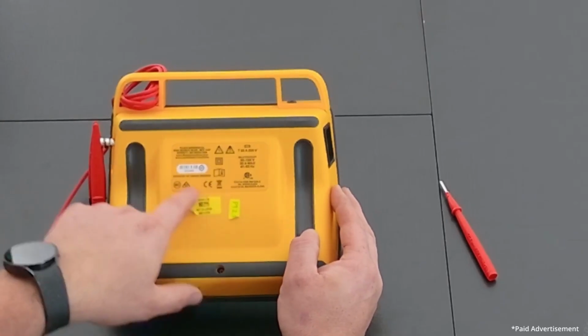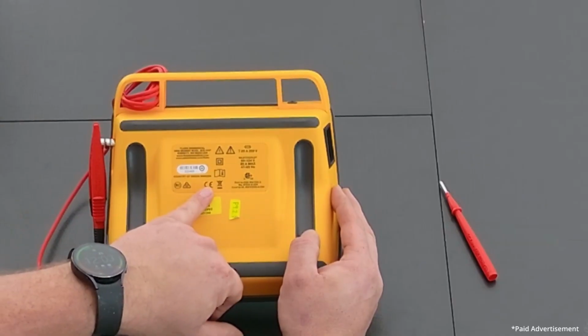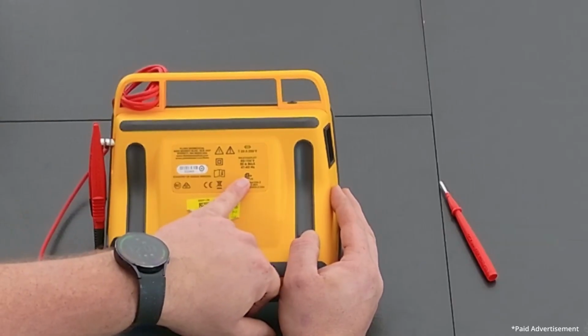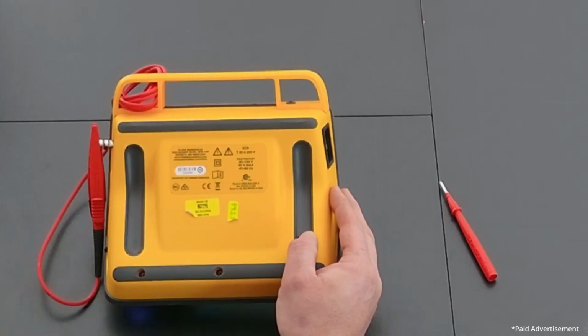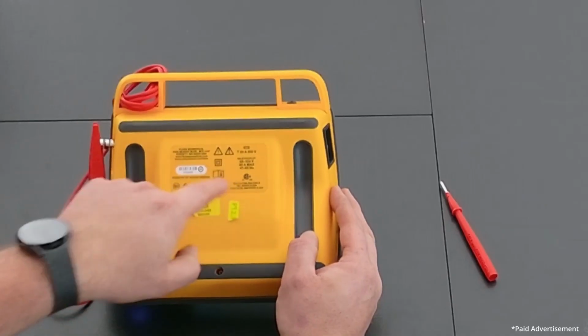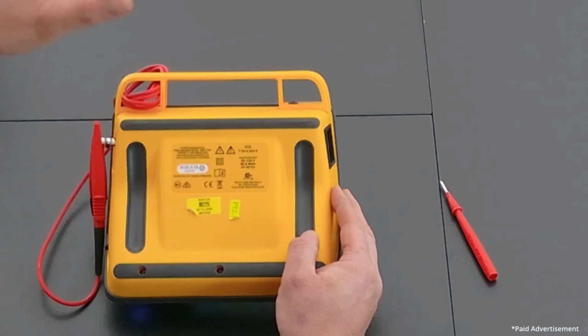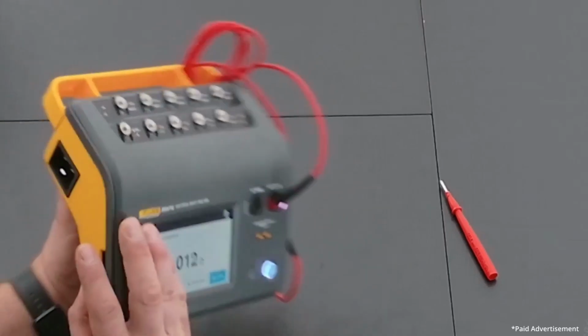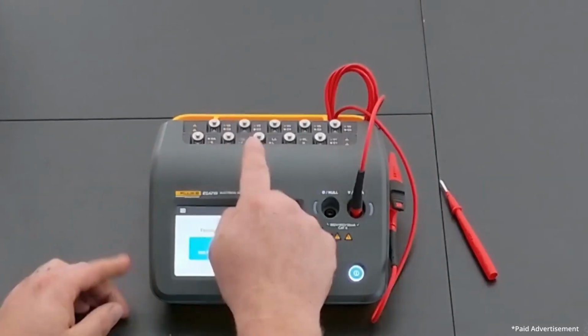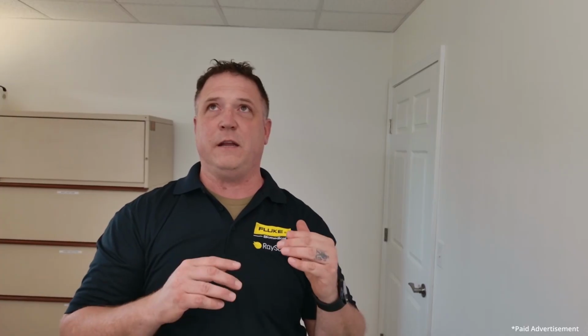Here on the back of my analyzer, you're going to see two stamps. Right here is a CE, and this one is a CSA. In order to get these two stamps, I must first be UL listed. So this is a higher level than the UL. So that's that "or higher" part. If you think about the laws of metrology, I'm supposed to use something of higher resolution to test something of lower resolution. Therefore, you wouldn't want to use a non-UL listed device to test a UL listed device. Ours is the other way around. We spent a little bit of time and effort and got that CSA stamp to test that UL listed device. So there's one thing in there, Danielle.